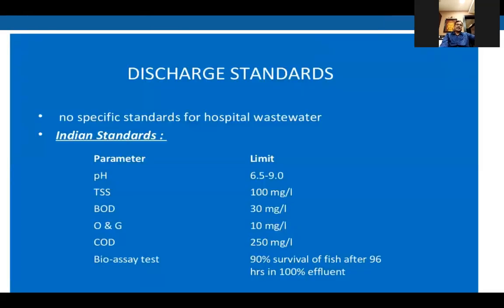Next, sir. So these are the discharge standards for STP water. I have just highlighted, but friends, on 19th of October we received a notification from the Government of India that these standards have now undergone change and have become more strict, especially for BOD. I have mentioned here 30 milligrams per liter, whereas it has become less than 20 milligrams per liter, especially in the metro cities. And total suspended solids have gone to less than 50 milligrams per liter, whereas earlier it was 100 milligrams per liter, as you can see yourself. So some of the standards are becoming stricter, but the implementation of the STP water discharge criteria as a fresh one is up to 2019, and they have given all old hospitals 5 years to comply with the standards. Next, sir.